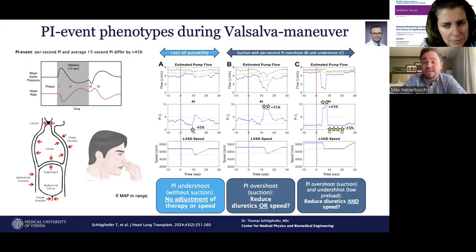So here they analyzed PI events, defined as moments when the per-second PI differs from the 15-second average by more than 45%. And now here in the three panels on the right, we see distinct PI response phenotypes. In panel A, for instance, we see a simple PI undershoot. That means flow and PI drop slightly during the maneuver, but without any suction event occurring. And those patients typically need no adjustment in therapy or speed.